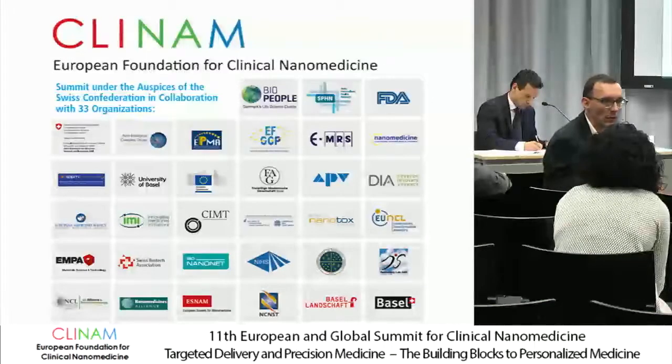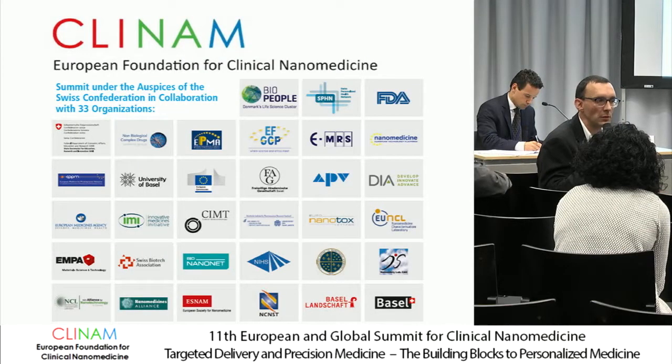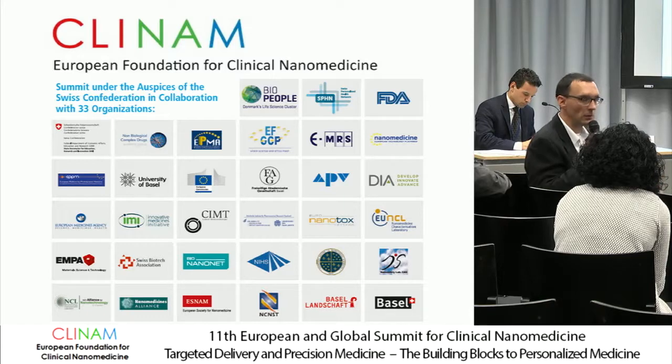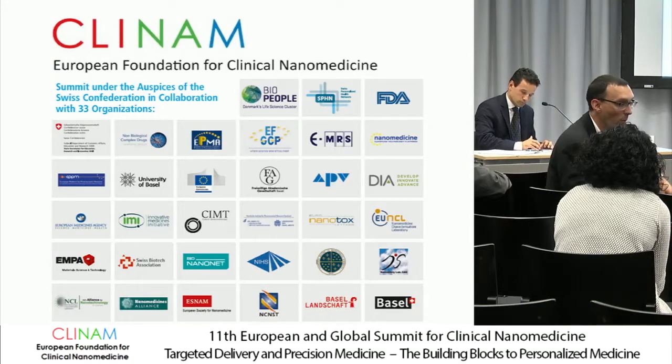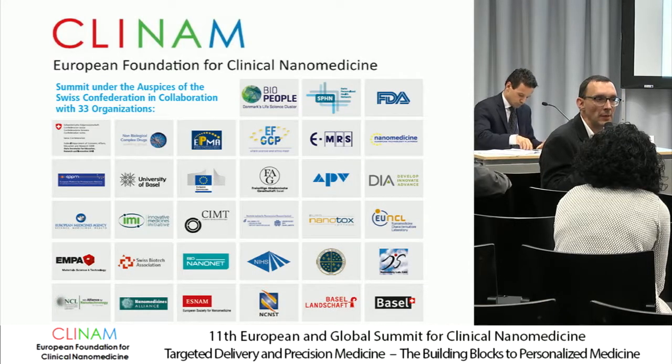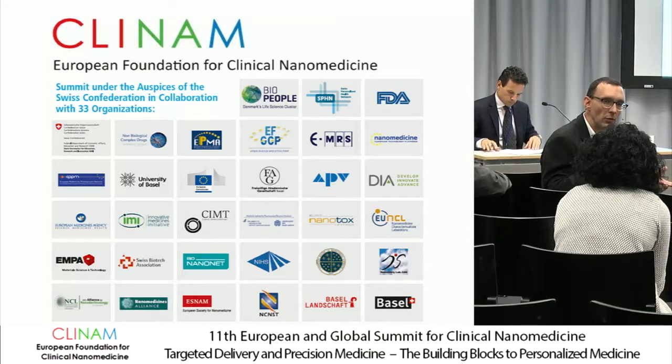a recommendation, if we come to a discussion, is to first check the instrument with a standard you can really derive back, like polystyrene. You measure that, you have the mass concentration, and you trace back to the number concentration. This is what you can trace back. Then you know that your instrument is actually working.